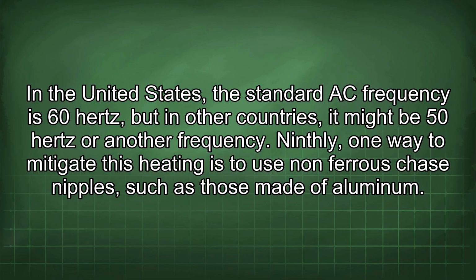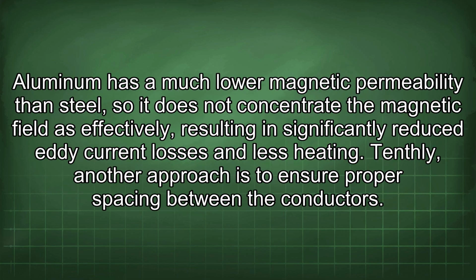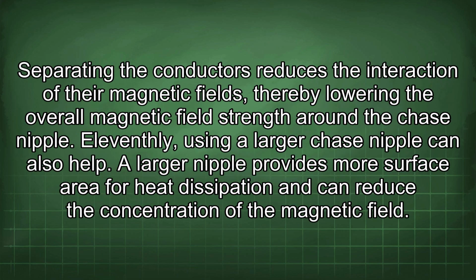Ninthly, one way to mitigate this heating is to use non-ferrous chase nipples, such as those made of aluminum. Aluminum has a much lower magnetic permeability than steel, so it does not concentrate the magnetic field as effectively, resulting in significantly reduced eddy current losses and less heating. Tenthly, another approach is to ensure proper spacing between the conductors. Separating the conductors reduces the interaction of their magnetic fields, thereby lowering the overall magnetic field strength around the chase nipple. Eleventhly, using a larger chase nipple can also help.